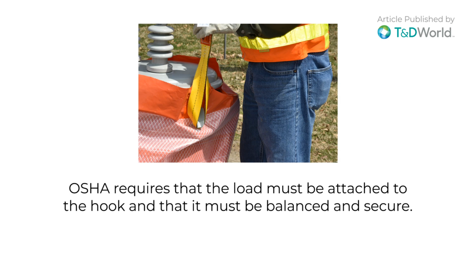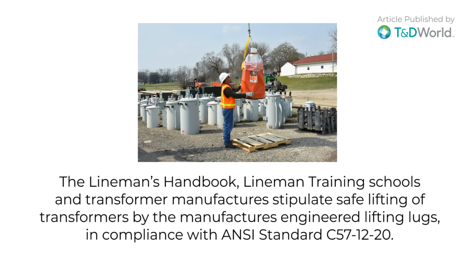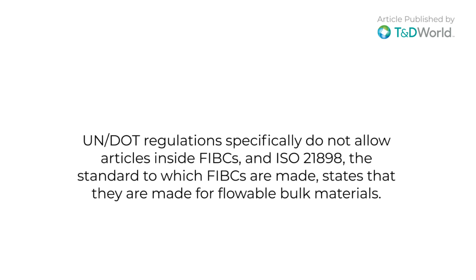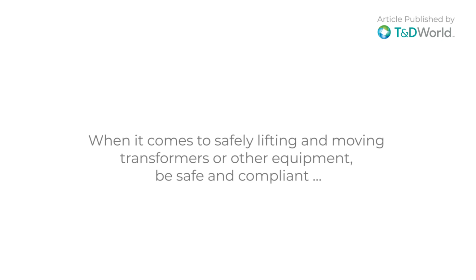OSHA requires that the load must be attached to the hook and that it must be balanced and secure. The Lineman's Handbook, lineman training schools, and transformer manufacturers stipulate safe lifting of transformers by the manufacturer's engineered lifting lugs. In compliance with ANSI Standard C57-12-20, UN/DOT regulations specifically do not allow articles inside FIBCs, and ISO 21898, the standard to which FIBCs are made, states that they are made for flowable bulk materials. When it comes to safely lifting and moving transformers or other equipment, be safe and compliant. Lift it by the lugs.